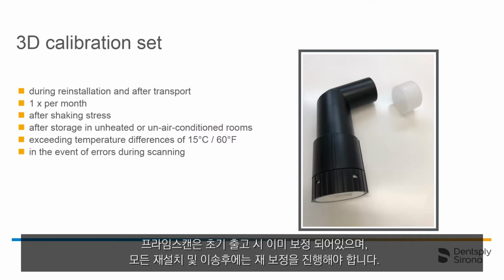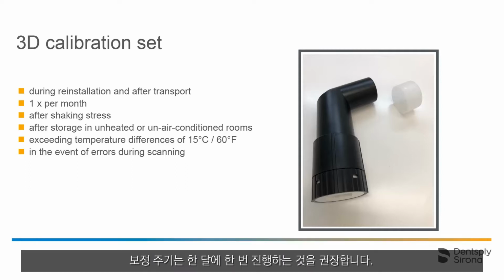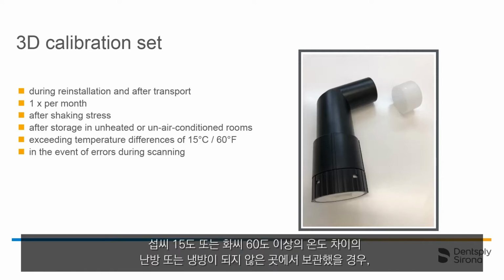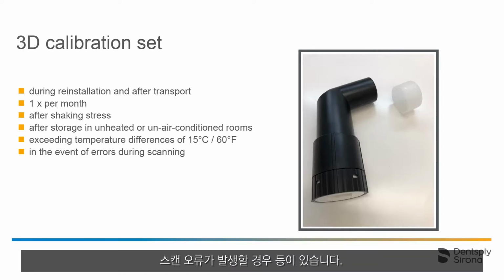PrimeScan is factory calibrated. The scanner should be recalibrated following every reinstallation and every transport. Thereafter, it is recommended to perform a calibration once a month. There are several other reasons why recalibrating is necessary. For example, following shaking stress during transport, after storage in spaces that are not heated or air-conditioned, with temperature differences of more than 15 degrees Celsius or 60 degrees Fahrenheit, and in the event of scanning errors.